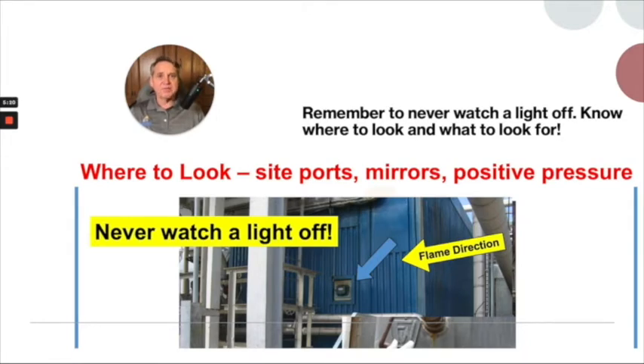To really observe a flame and get useful information, you need to have the flame coming at you. This is the back of a boiler shown here. Some sight ports open right into the firebox — very dangerous. If you have a change in firebox pressure, you could get hot flue gases coming out and hitting you in the face. Sometimes people use mirrors, protective gloves, and special flame-resistant clothing at those sight ports. In other cases, there's a piece of tempered glass — always check with a gloved hand first, make sure there's no leakage, that the glass is intact and clean. Only with proper PPE and safety glasses should you bend down and look through. And never look during a light-off — there have been people horribly injured by firebox explosions.